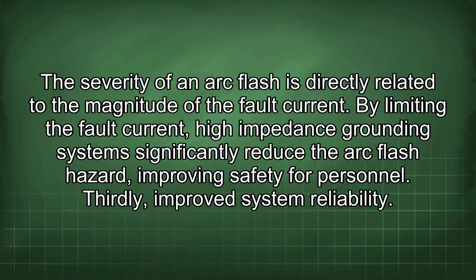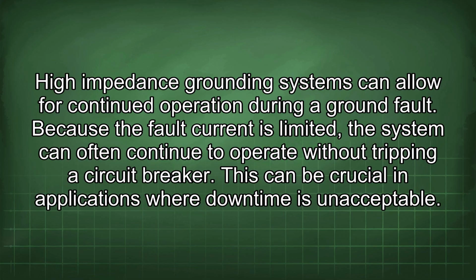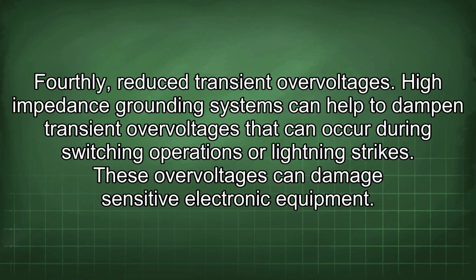Thirdly, improved system reliability. High-impedance grounding systems can allow for continued operation during a ground fault. Because the fault current is limited, the system can often continue to operate without tripping a circuit breaker. This can be crucial in applications where downtime is unacceptable. Fourthly, reduced transient overvoltages. High-impedance grounding systems can help to dampen transient overvoltages that can occur during switching operations or lightning strikes. These overvoltages can damage sensitive electronic equipment.